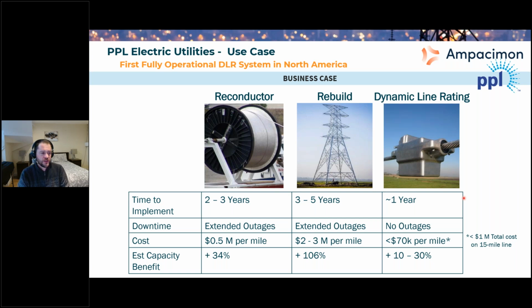That gives you, in this example, 10 to 30% extra capacity on that line. So even if they were going to reconductor, it bought them some time — they got a little extra capacity and deferred that asset upgrade. Similarly, on some lines, they've been able to install DLR and completely negate the need to reconductor, just because of that extra 10 or 20%.